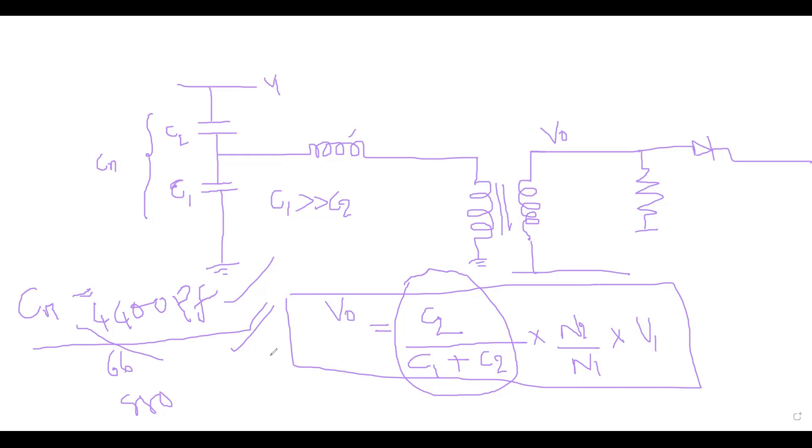3P class, 0.2S class, everything all similar. The only thing here addition is the capacitor value that generally for 220 KV it is 4,400. For 400 KV above you can see 6,600 and above you can see 8,800 picofarads.